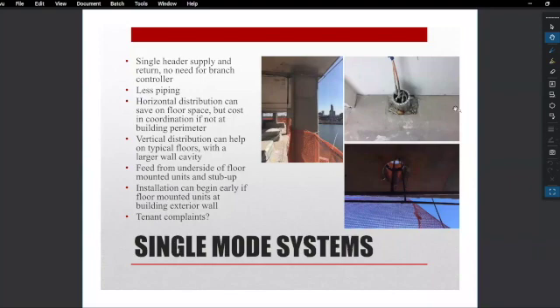And it's a pretty simple system. It's not a lot of piping. You're basically using one header, and there's a takeoff from every header to distribute to the fan coil unit. One of the complications at Cornell was since we had that horizontal penetration to the condensing unit, the condensing unit was in a pseudo exterior space. So all of those penetrations needed to be air sealed. So that was another situation where we had a typical condition at every floor that also needs to be QA/QC'd.